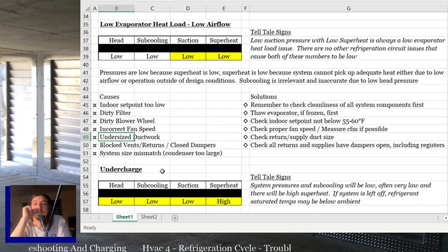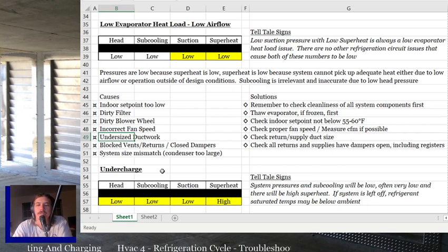Right. Yeah. It's low evaporator heat load almost every time. It's almost always low airflow. It might be an undercharge. It might just be an undercharge, because it does happen if your charge is just right, okay? If your undercharge is just right so that your suction's running right at about 32, you might have that happen. I've seen it, I want to say, once or twice. But it's almost always something wrong on the airflow side of the evaporator, because that's what causes the line to freeze.